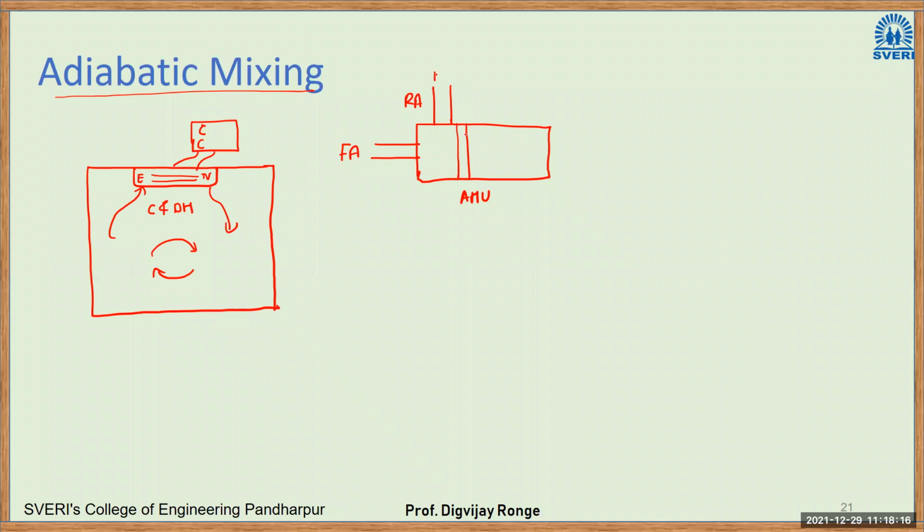Then they are filtered. Then there is a coil section where they are cooled. If required, there is another section for a heating coil, where they are heated again. Then we have an outlet with a blower fan. This outlet is termed the supply air.